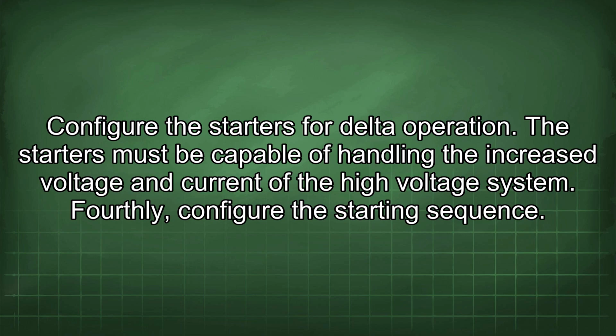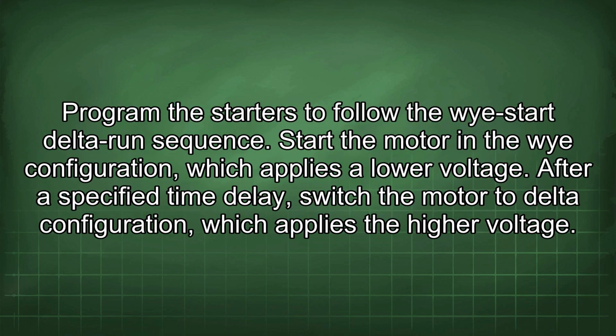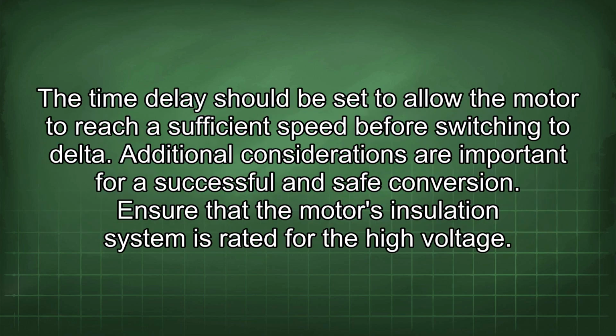Fourthly, configure the starting sequence. Program the starters to follow the Wye-Start delta run sequence. Start the motor in the Y configuration, which applies a low voltage. After a specified time delay, switch the motor to delta configuration, which applies the higher voltage. The time delay should be set to allow the motor to reach a sufficient speed before switching to delta.